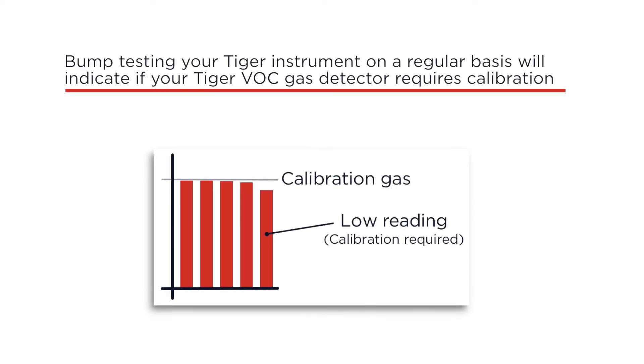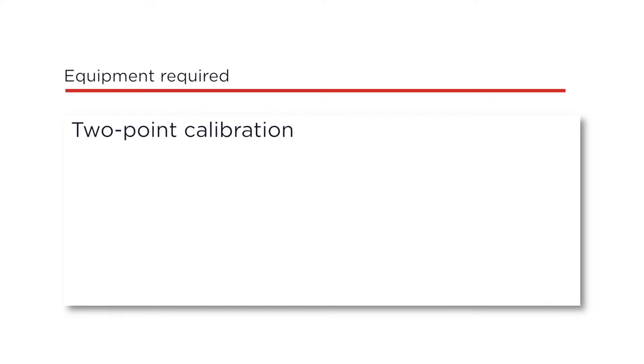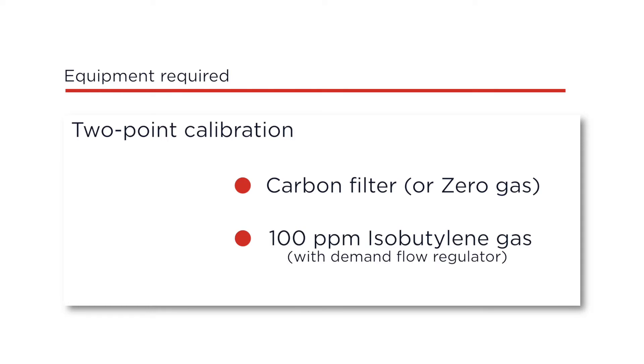Bump testing your TIGER instrument on a regular basis will indicate if your TIGER VOC gas detector requires calibration. In this example, a two-point calibration will be carried out using a carbon filter for zero and 100 ppm isobutylene for the span.